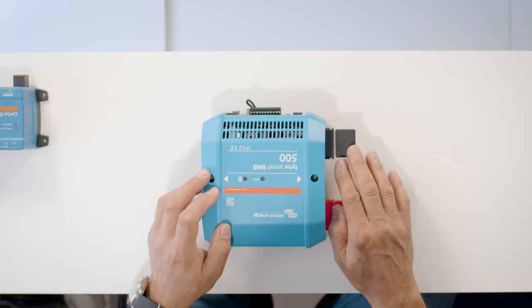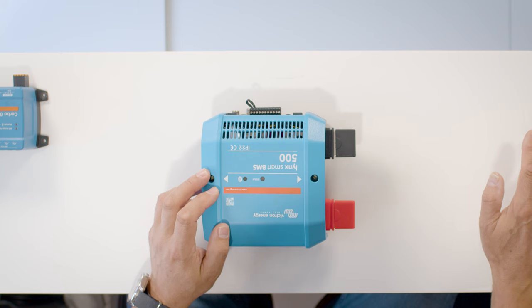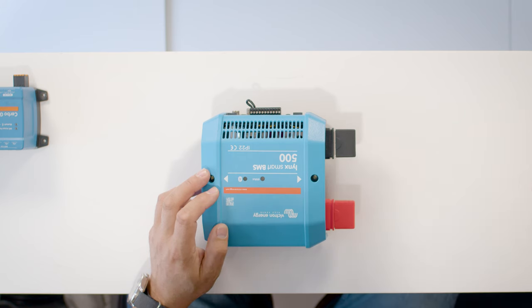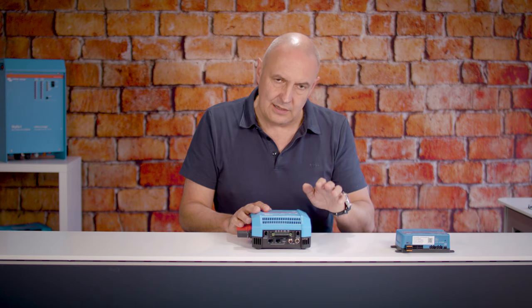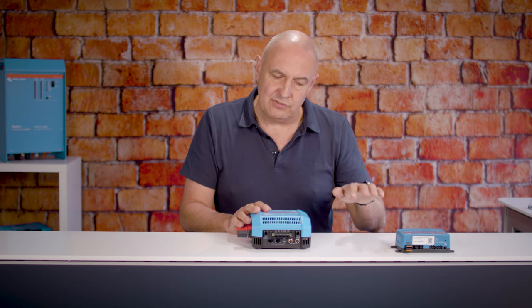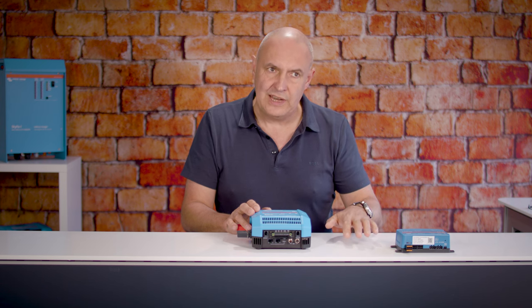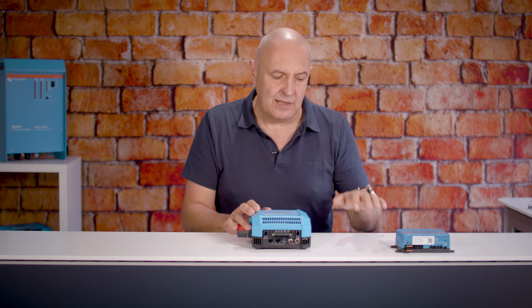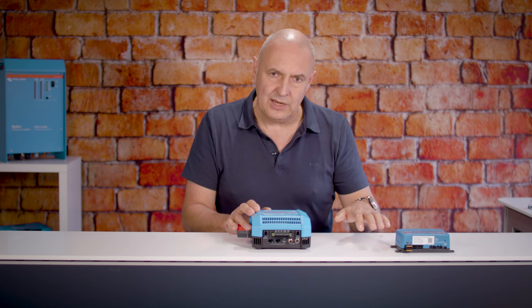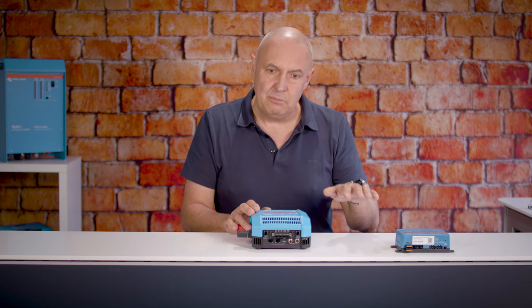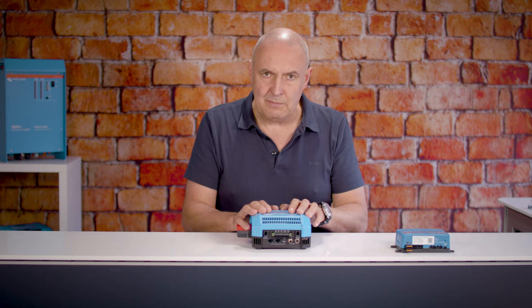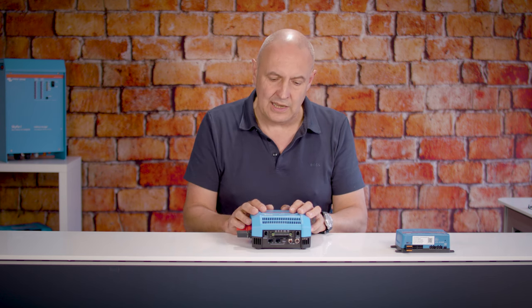The Lynx Power In is effectively just two busbars, a positive and a negative busbar, and it allows you to connect four batteries and link those through each of those batteries with its own stud terminal. The Lynx Distributor has fuses and fuse failure detection built into it, and we'll talk a little bit about how that communicates that information back through the Lynx Smart BMS and off to the system in a little bit.